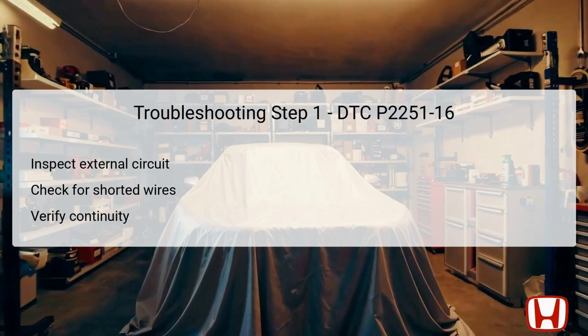The first troubleshooting step involves inspecting the external circuit associated with the AF sensor. This includes examining the wiring harness for any signs of damage, frays, or wear that could facilitate a short-to-ground condition. It's important to carefully check each wire in the voltage signal circuit, looking for any points of contact that may be shorts. Additionally, verifying continuity through a multimeter is crucial.